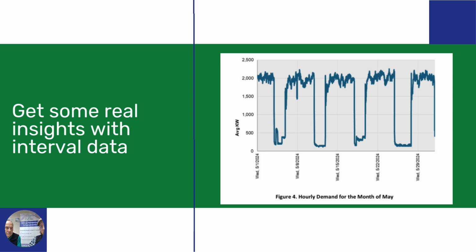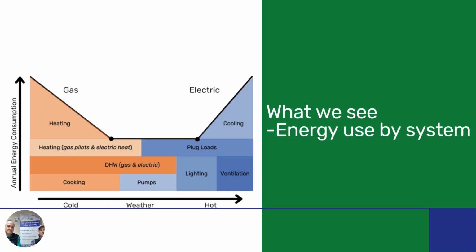It looks like they have a drop off here at some point, and this is over the weekend, which gives us a second set of visibility into that interval data to substantiate that there's 250 kW that they're never getting to zero. Right. So if viewing the data one way, you may be concerned, is there an anomaly there, or is there a trend that maybe I'm reading too much into the data? This is just another way to slice the data, and the pie tastes the same.